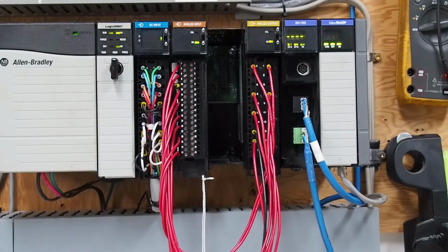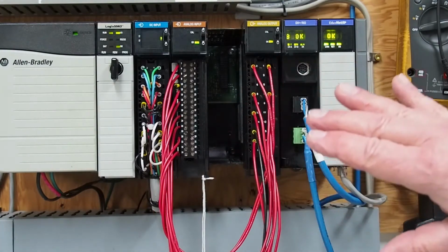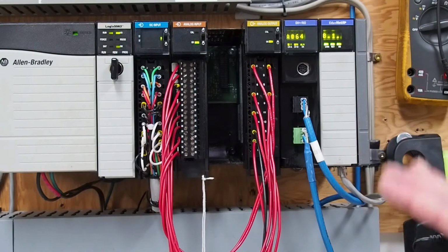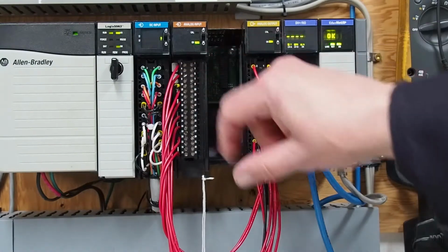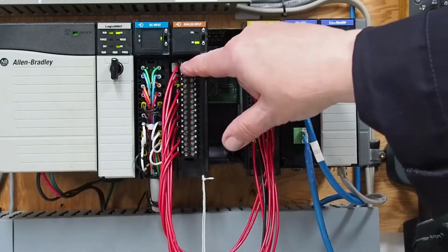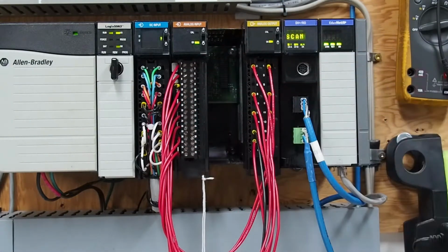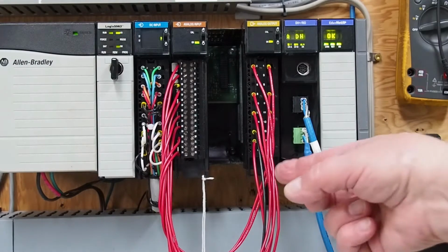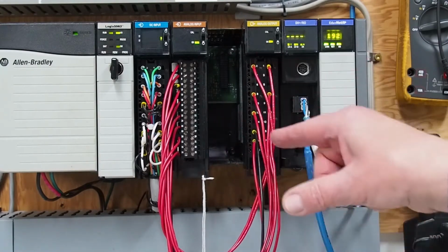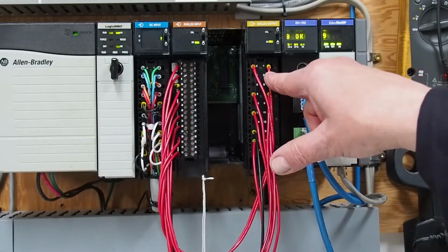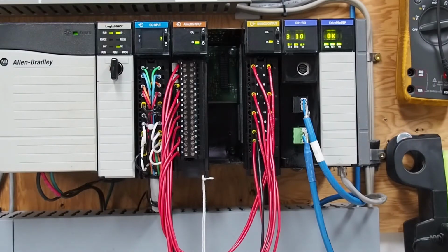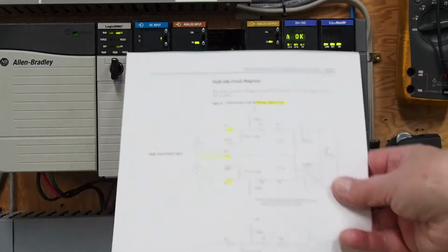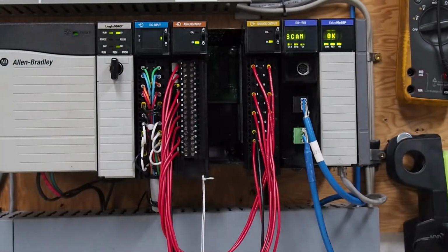All right, we're back, and here's the chassis. So here's my analog voltage test setup. I have an OF8 fitting into an IF16. Each channel on the OF8 is tied to two inputs on the IF16. The common is common on all points on the OF8, and the common is also common on all four points on the IF16. So if we look at the wiring diagram...